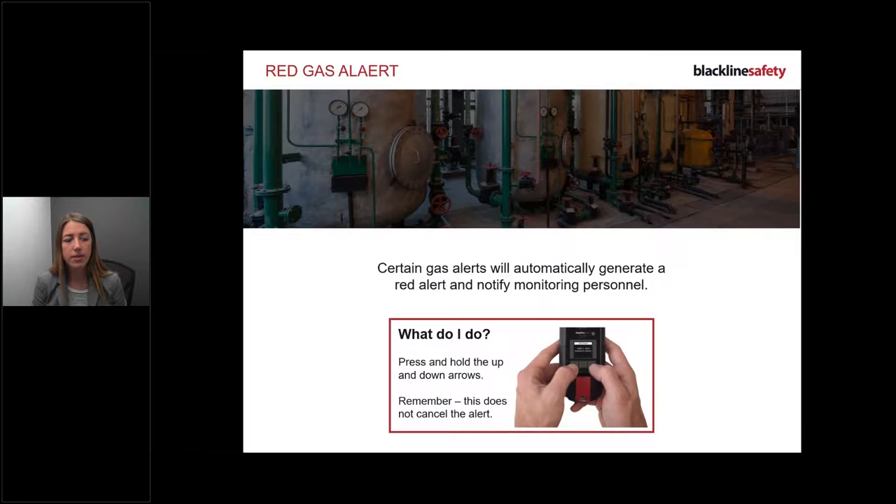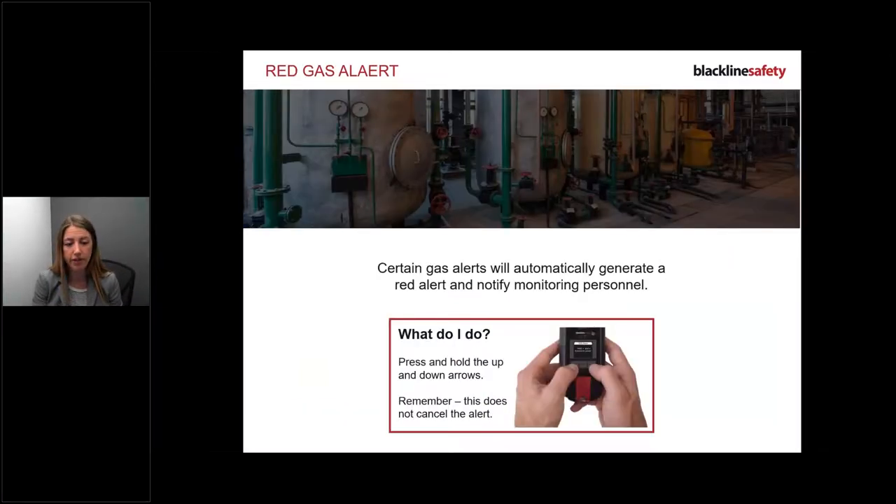For gas detection alerts, a red alert comes in just like pulling the latch. When you get that red gas alert, evacuate immediately - get out of that situation right away. Then you can read the screen. The gas alert types include: STEL, high alert, TWA, and over-limit. These are the four alert types we respond to. Evacuate first, then read the screen, then silence.